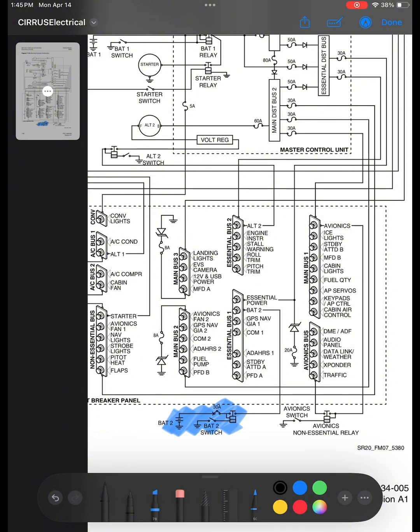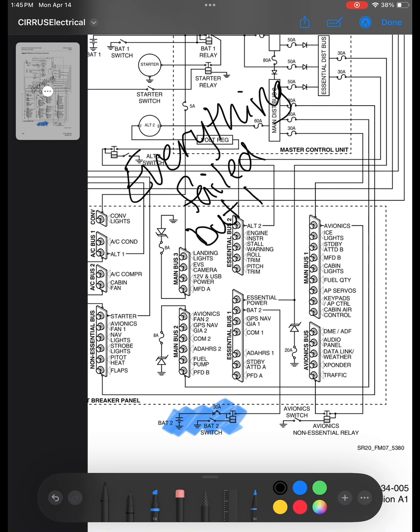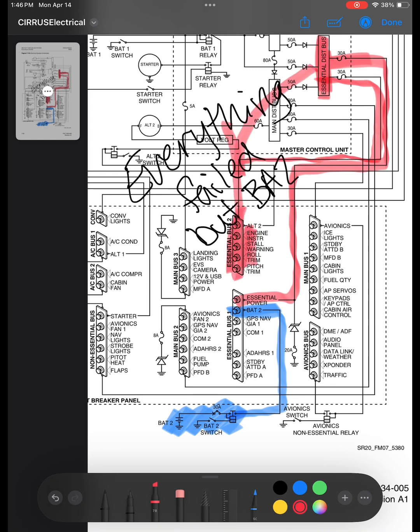So let's say that battery 1, alt 2, everything has failed except for battery 2. Well, that switch will kick on, that relay will connect the circuit, and battery 2 is going to start directly charging essential bus 1. Now, the power does travel back up. It will power the whole bus, but it's also going to send it back through to the essential distribution bus, which would then power essential bus 2. Keeping in mind there's always a direct current to essential bus 1, but essential bus 2 is charged or given electricity via the essential distribution bus.